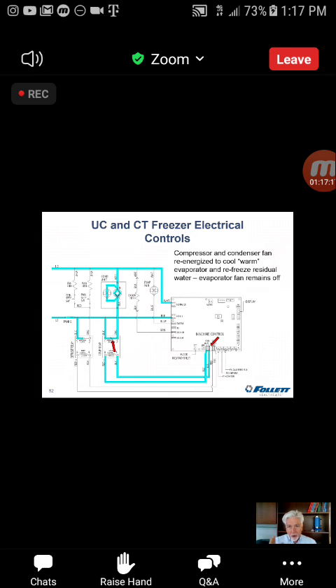Well, think about this. We have a coil now that's at 5 degrees C. We probably have product out in the storage compartment that's at -20. So we don't want to be sending that heat out to where our product is. So we're only going to energize the compressor and the condenser fan motor to cool that unit down. We're going to run that refrigeration system for 30 seconds, and at the end of the 30 seconds, that is when the fan is re-energized. So typical defrost time is 6 to 8 minutes. That's all it should be. It should not be getting anywhere near the limit.